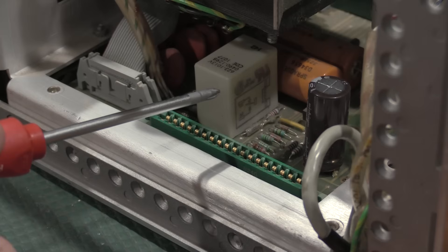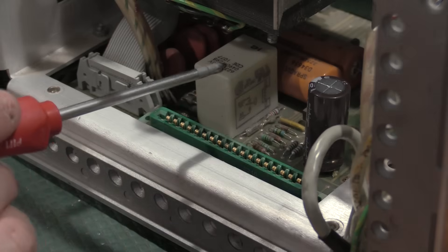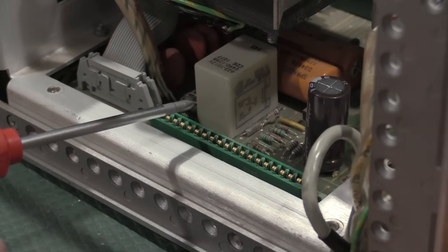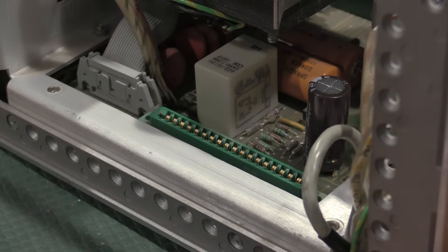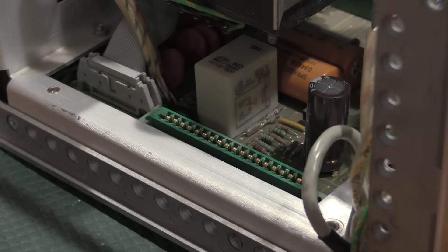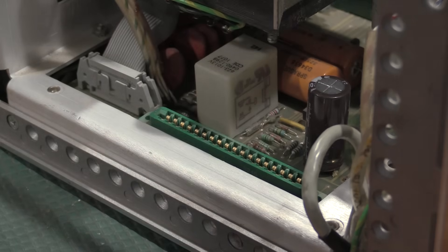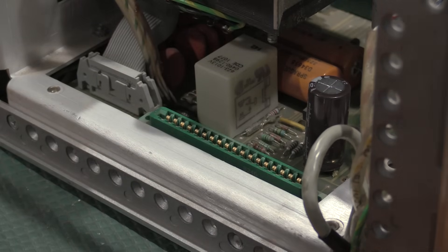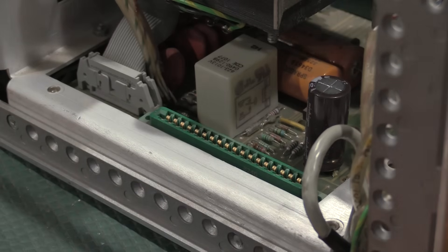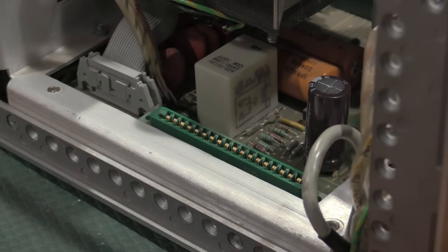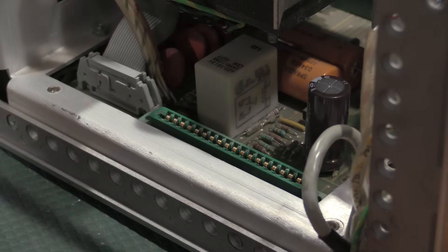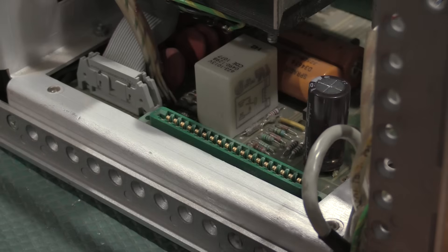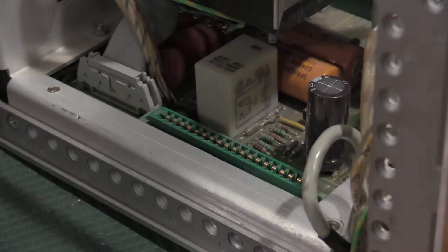It looks like it goes into somewhat of a biasing network because the relay spawns off to one of the boards through the connector. And on the other side of this relay, we also have some biasing resistors, capacitors, and a zener that also go there and are fed by the plus 20 volts unfiltered rail. One thing that could cause this resistor to burn down like this would be if one of those zener shorted and all of a sudden it loses a reference and goes absolutely nuts and decides to burn down. That has happened before on this channel, actually. On my fluke 5200 a one of the high voltage 190 volt zeners shorted out and took cascade failure, the negative 190 volt rail. So something we have seen before and is not completely uncommon.